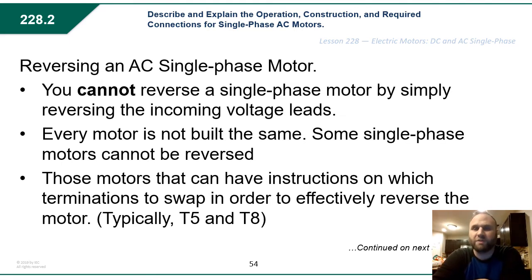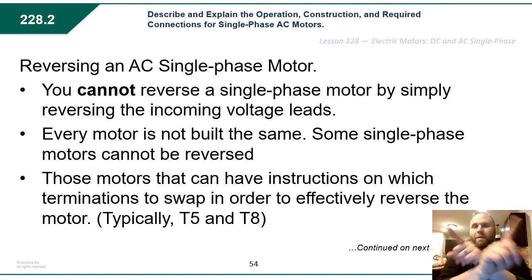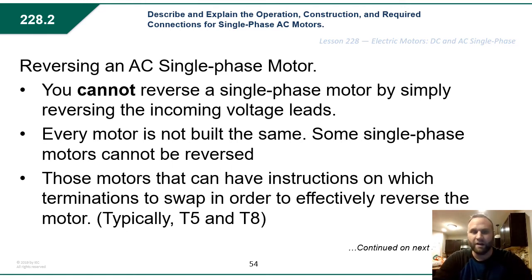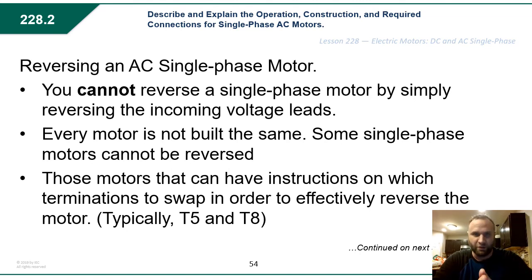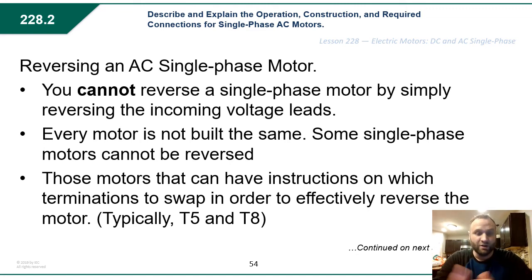When it comes to reversing an AC motor, you can't reverse it by simply swapping the leads coming in like you could with a DC motor. Every motor is not built the same — some single-phase motors cannot even be reversed. So check that before you try to swap leads around; you may have a motor that is not reversible.